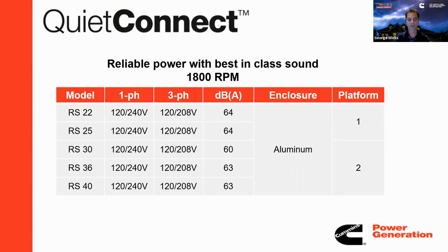If you saw the acoustical center, they were setting up microphones - they run 8 microphones around the unit at 45 degree increments, so we're picking up the average of those 8 microphones at 23 feet apart at full load. In the fine print of a lot of our competitors, they're not going to tell you that - they might be running at a rated load, a half load, or even a no load. Our commercial liquid cooled generators are rated at full load sound.